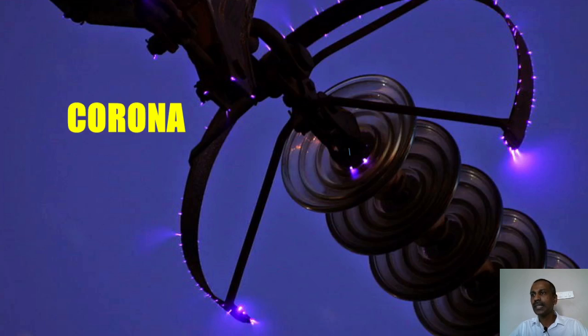Hi students, in this class we are going to study the phenomenon called corona in the transmission line. During the normal working condition, the air surrounding the transmission line consists of ionized particles.